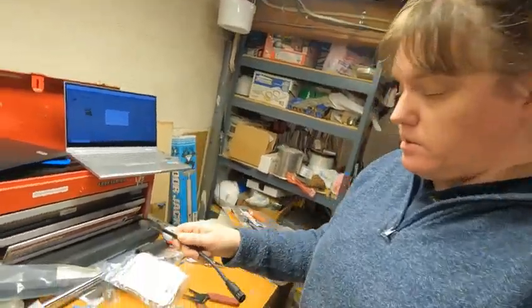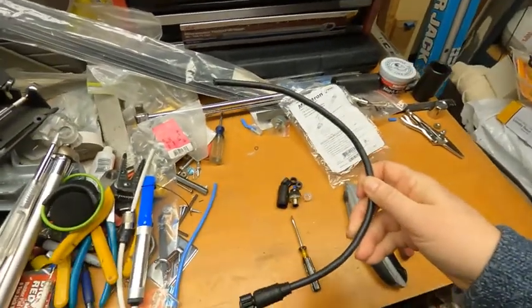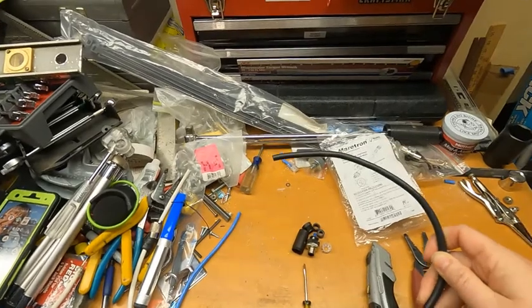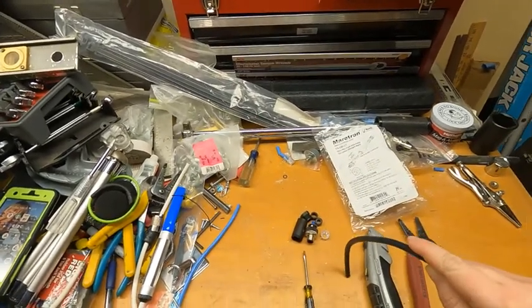Hey class, this video is going to go over how to do a NMEA 2000 field connector. We would use these in a place where we had to cut a connector off because it wouldn't fit through a hole, and we needed to cut the connector off to fit just the bare wire through. So let's say we had a small hole — that connector would not fit through, but the wire will. Cut the connector off and then we can feed that through the hole.